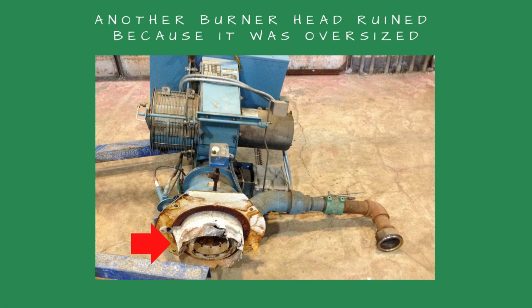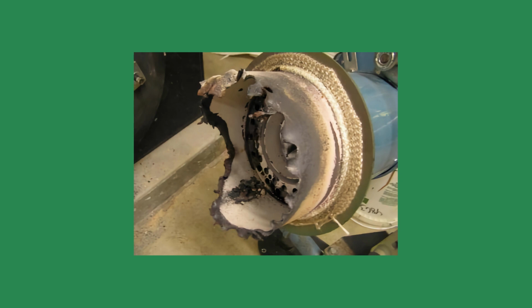What do you think is causing the heads to warp? I asked. I contend most techs know the solution to the problem. They just don't know they know it. I wanted to see if he had the same theory as me. Shrugging his shoulders, he said, I think it's oversized because the boiler loafs along at low fire all winter long.